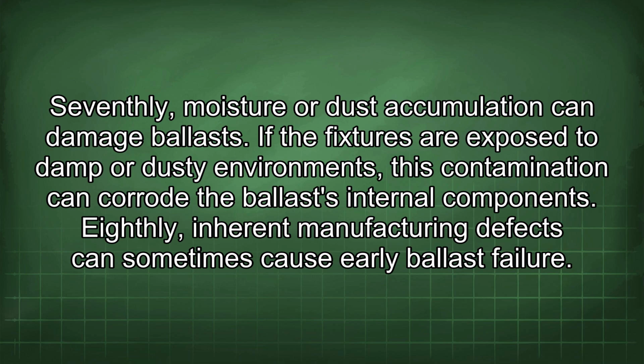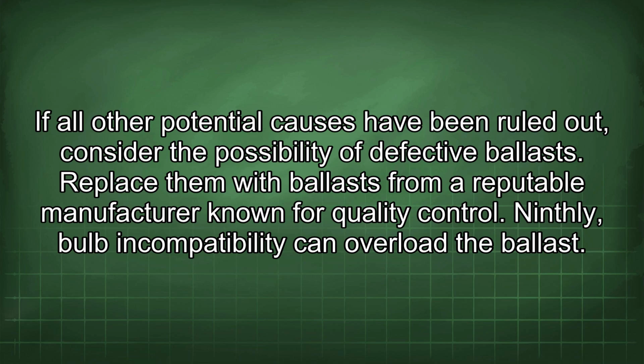Seventhly, moisture or dust accumulation can damage ballasts. If the fixtures are exposed to damp or dusty environments, this contamination can corrode the ballast's internal components. Eighthly, inherent manufacturing defects can sometimes cause early ballast failure. If all other potential causes have been ruled out, consider the possibility of defective ballasts. Replace them with ballasts from a reputable manufacturer known for quality control.